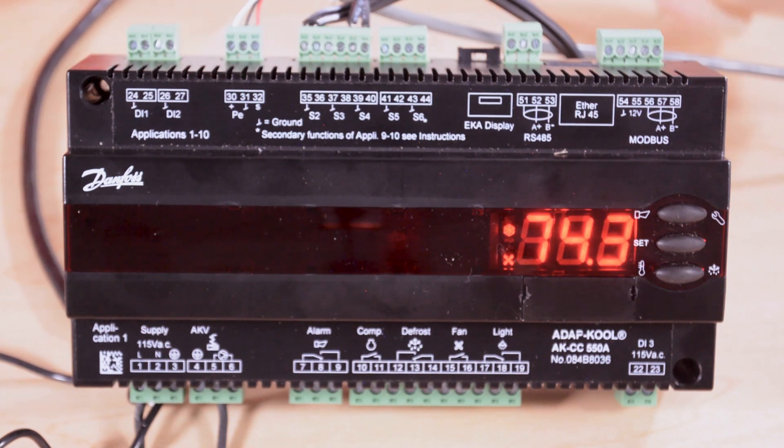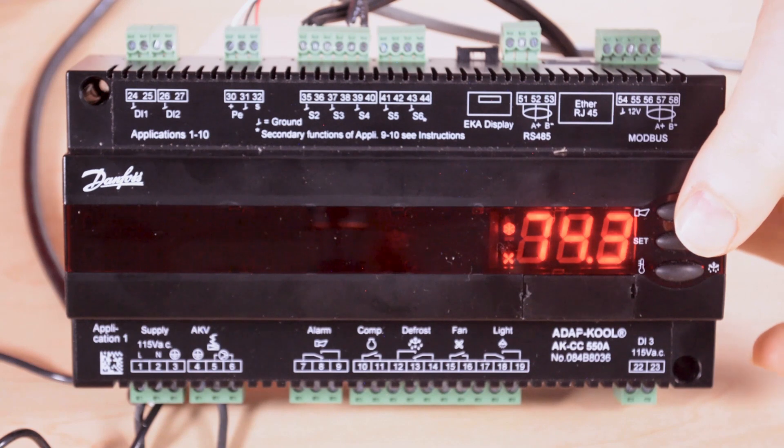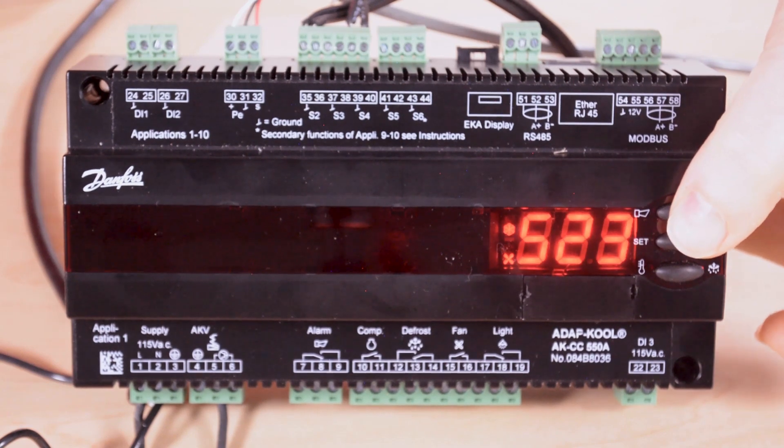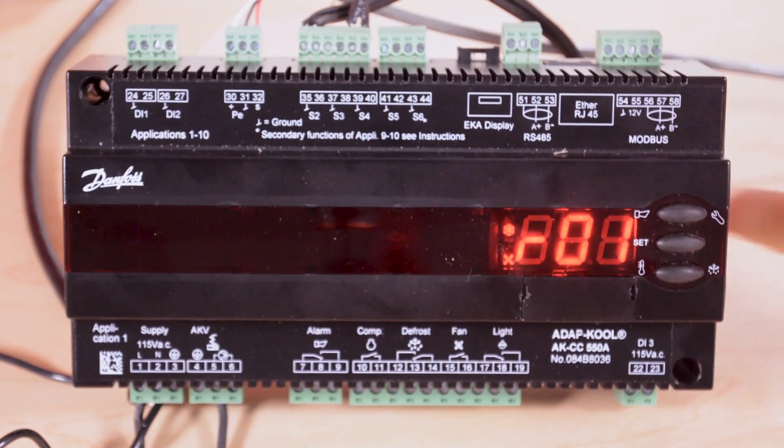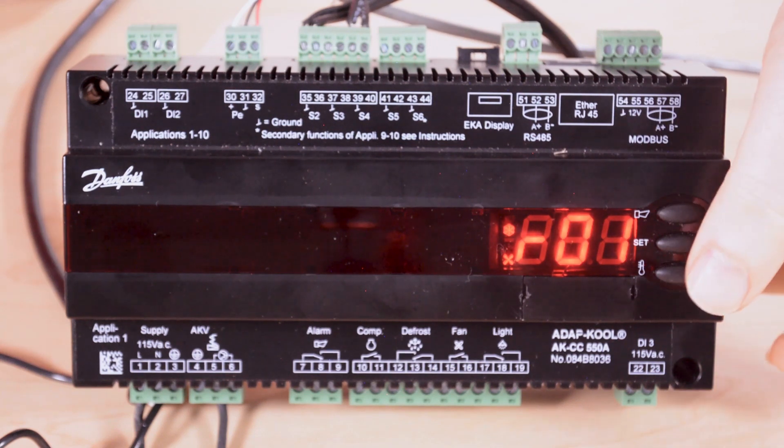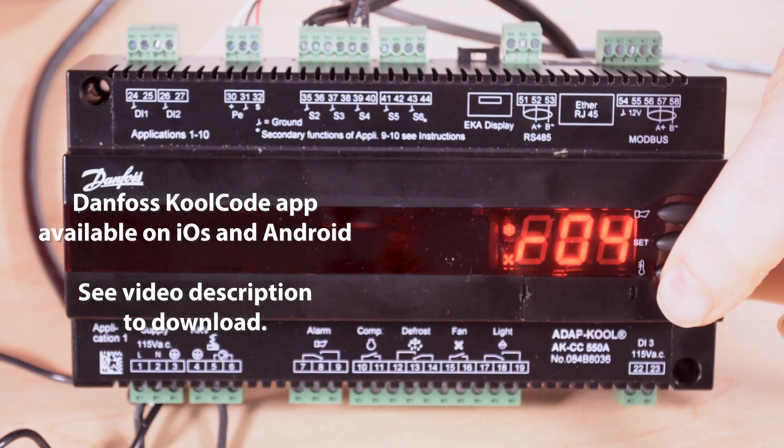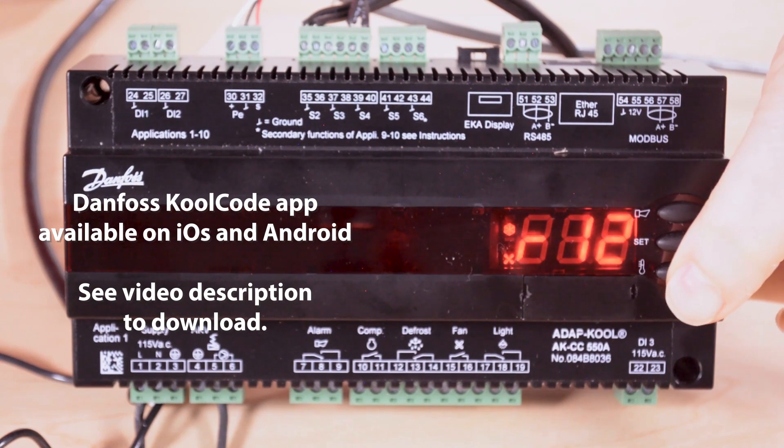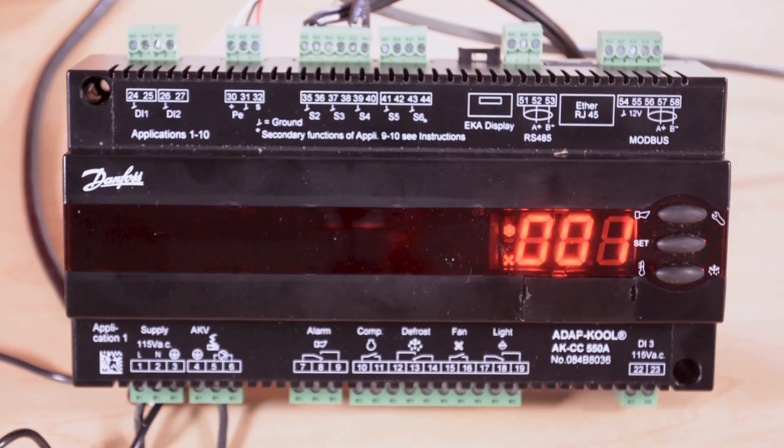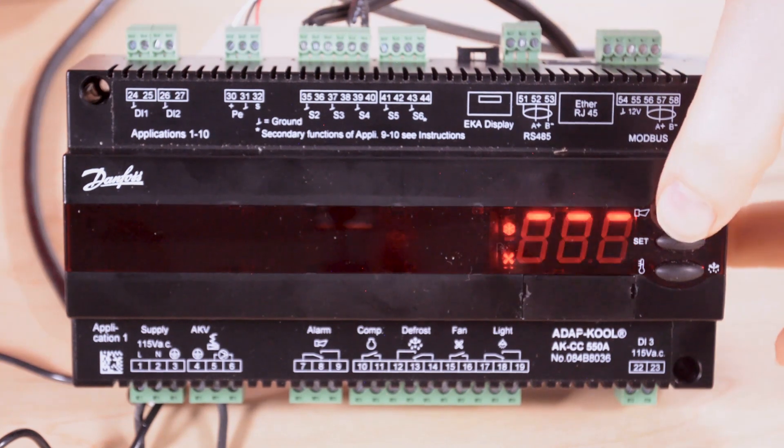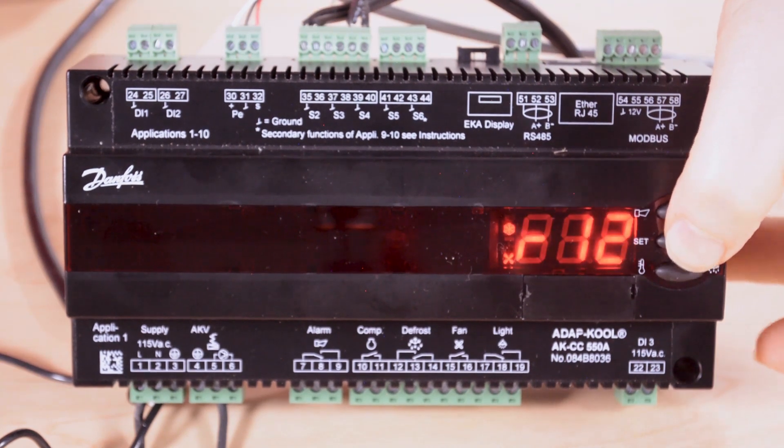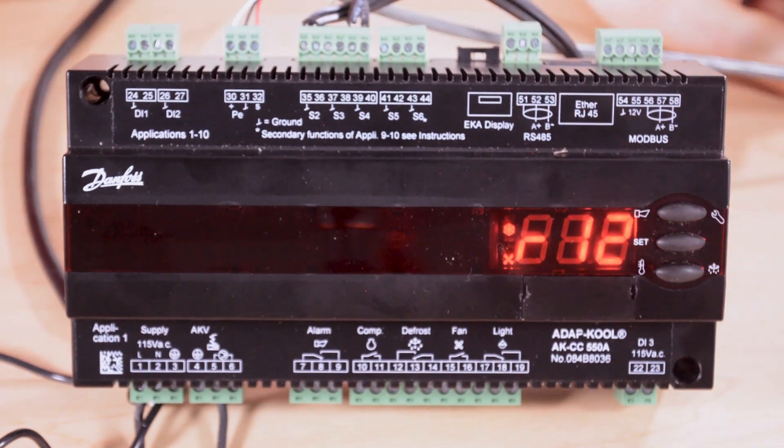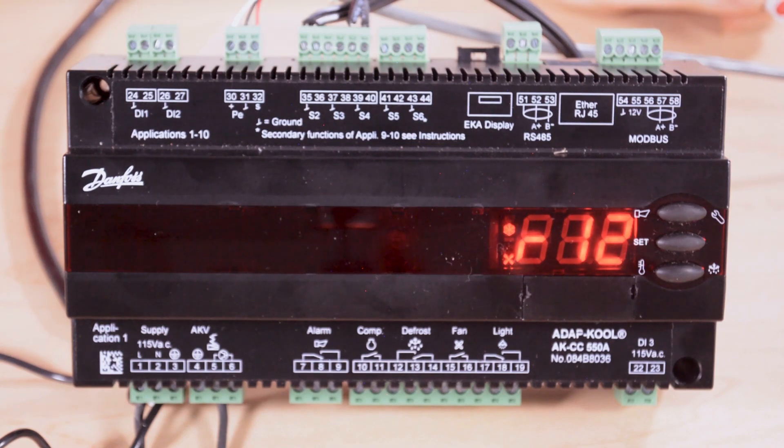The parameters can be accessed by holding the top button down until you get through the status codes and the alarm code. Now that we're in the parameter list we can go down through the parameters. If we want to make a change we use the middle button and then hit the middle button again to save it. The controller will time out after 15 seconds.